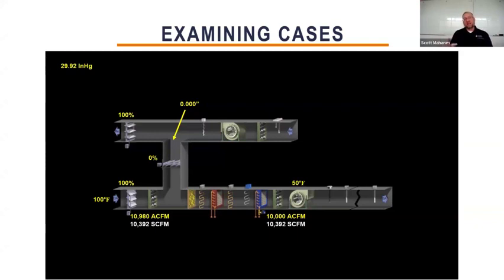And what's interesting is in volume, I can't compare the two. I can't allocate what's measured on the supply side to what's on the outside air because they're two different densities. I'm at 100 degrees on the outside air temp, 50 degrees on the discharge of the supply. But if I converted to the SCFM values you see, which is 10,392, I can compare the two.